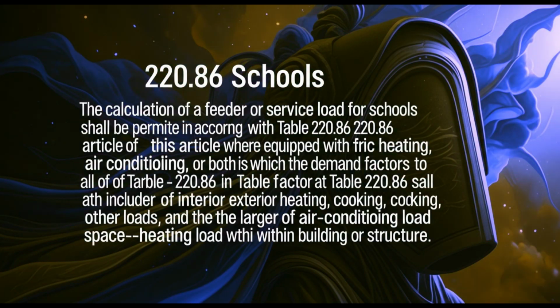So that brings us to this specific rule, Section 220.86. It's called the optional school feeder load calculation. Kind of specific, right? It is, and it's a fantastic example of the NEC really adapting to how buildings are actually used. A school's energy use isn't constant like, say, a factory running 24/7. Right. It has peaks, downtime. Exactly. Lots of diversity across the whole building. So this optional method lets you calculate the load differently than the standard, very conservative methods you find elsewhere in Part 3 of the article.